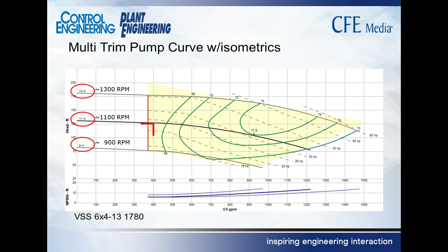It's how much energy does it take to get that mass moving. If you took the pump out and opened the valves up, the liquid is going to flow into the pump. So the energy provided for the velocity head on the suction side, in this case, is provided by the flooded suction, the fact that the suction head is a positive number. So if you took the pump out, the water is going to move. It isn't the pump that's got to provide the power to get the liquid moving. It's the gravity that does that. It's just the opposite if it's a suction lift. If it's a suction lift, then the velocity head is negative on the suction.